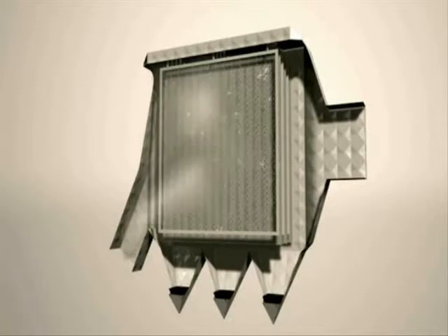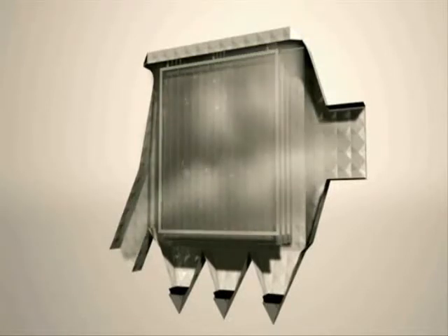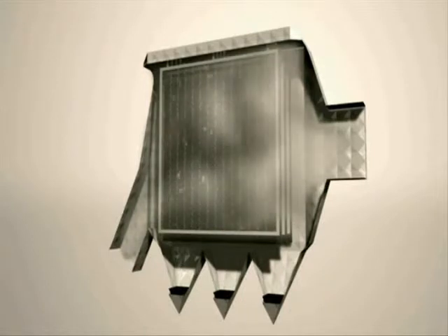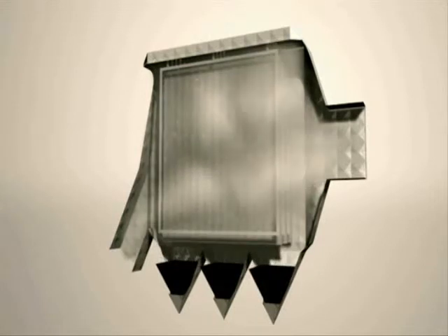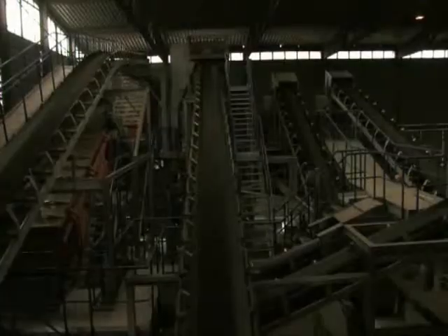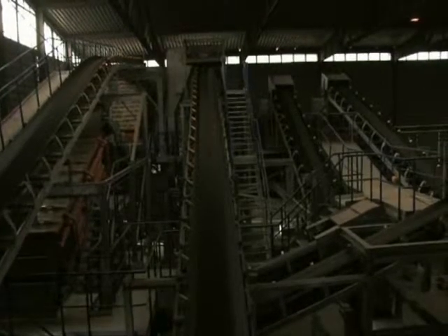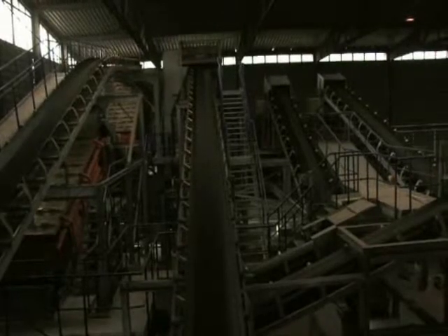The flue gas flows through the electrostatic precipitator, and the dust particles floating in the gas are electrically charged by the emission electrodes. Under the influence of a high-voltage electric field, the negatively charged particles of dust are attracted to the positively charged plates, the so-called precipitation electrodes. In order to clean, the plates are made to swing mechanically, whereby the dust falls into the collecting funnels underneath the electrostatic precipitator and is transported from there to the ash silo. After further treatment, the ash is also deposited together with the slag on the city's dump site.